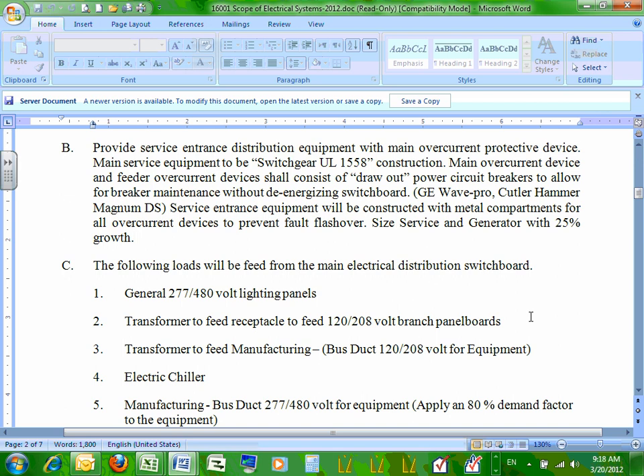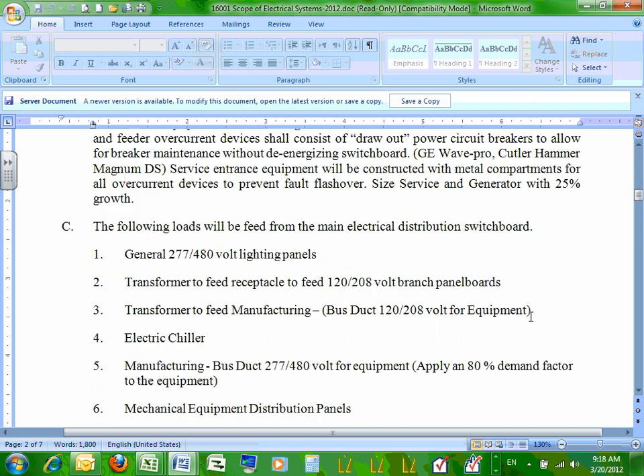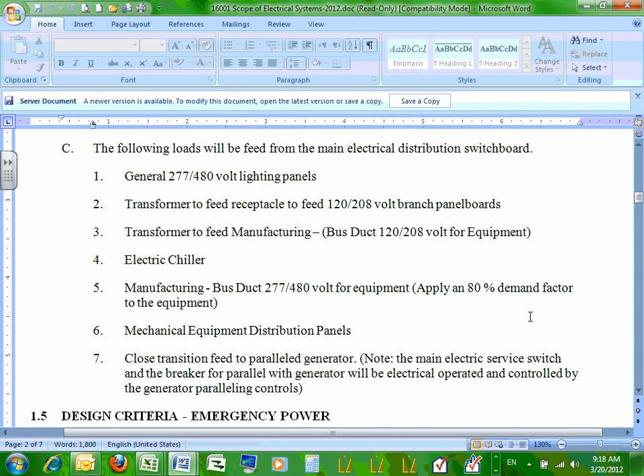Let's see here. When I talk about just some of the general pieces, we're going to have some 277/480-volt lighting panels. So the lighting will likely be 277. If you choose to do 480 someplace, that's your call, if you feel it's justified, but it will likely be 277. Then we have 120/208-volt transformers feeding panels for all our light circuit needs and receptacle needs.